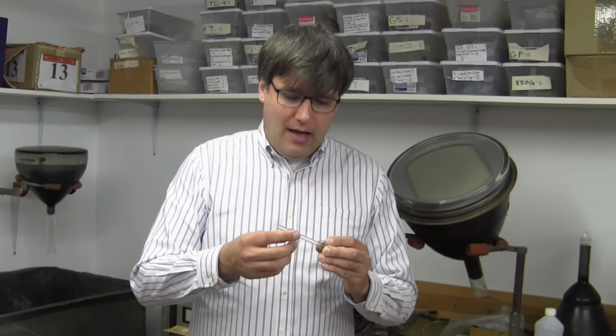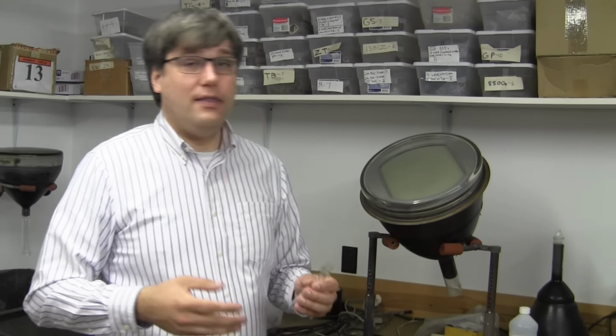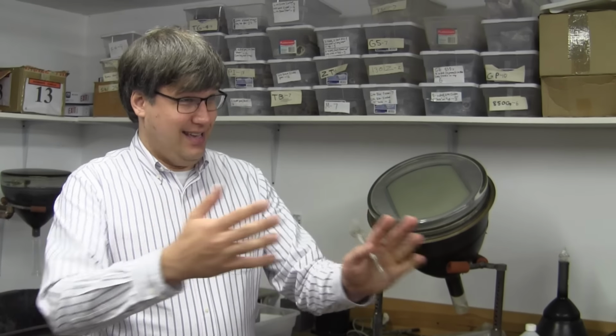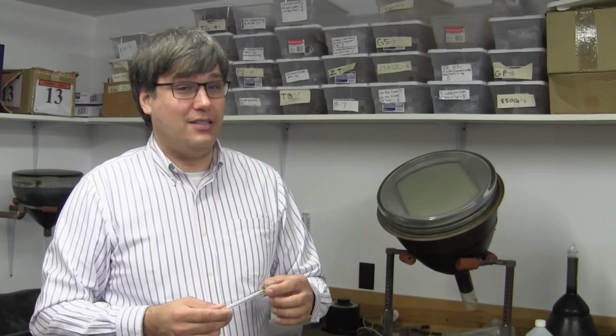The whole tube has to be baked in an oven up to approximately 200 C, hot. Everything in the tube has to be rated to those high temperatures. And it's left there for, the longer the better, to get all the residual gas to come out of the tube. And so you're pumping on it the whole time. And during that heating, the envelope of the tube has to survive the heat of the furnace and simultaneously has to hold the vacuum.